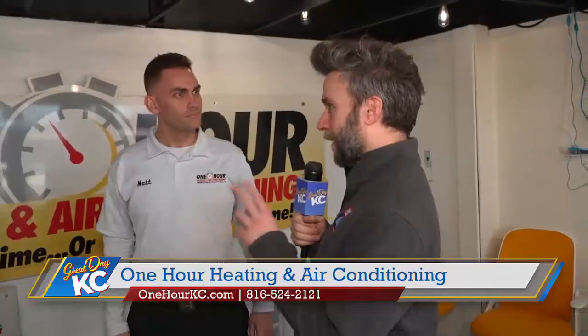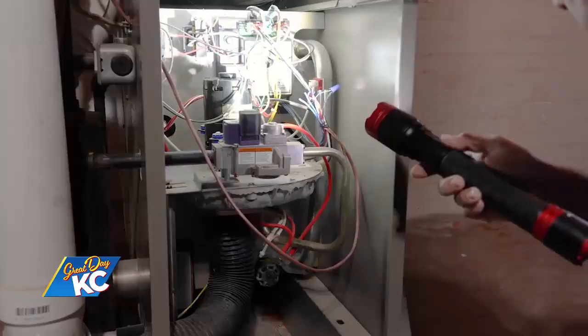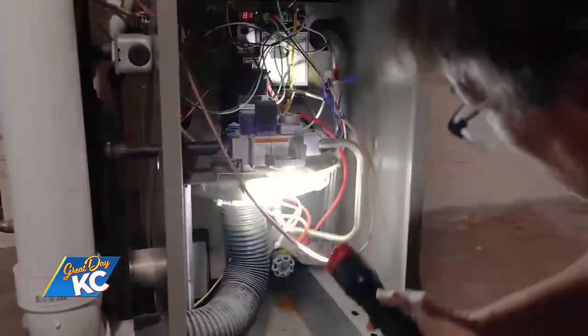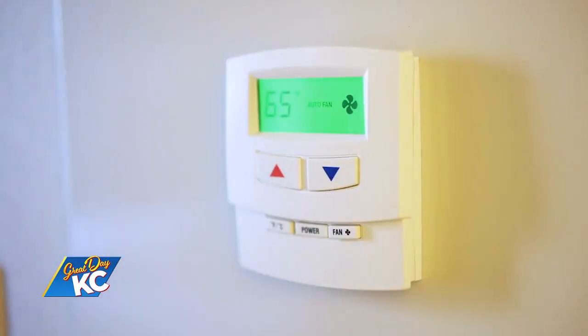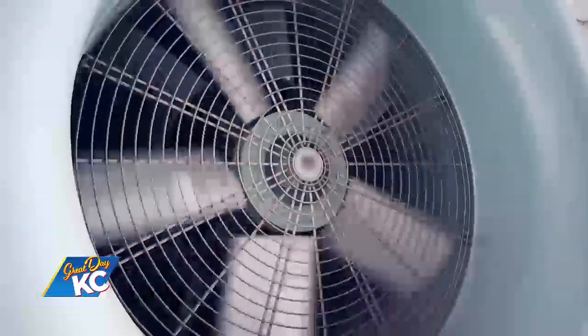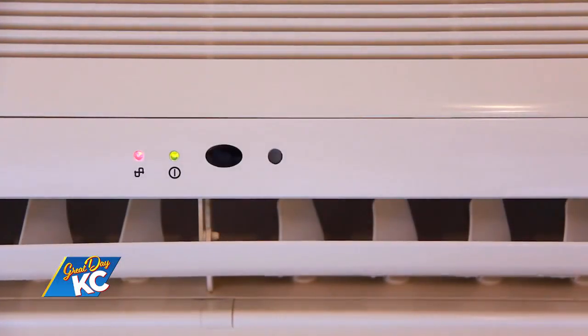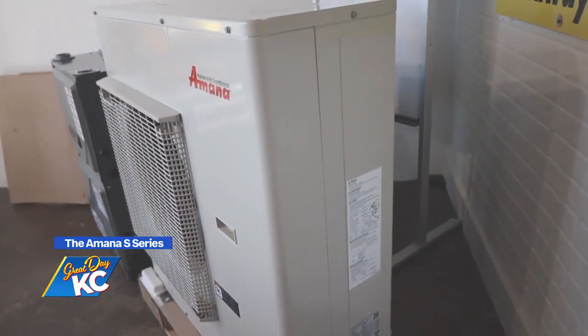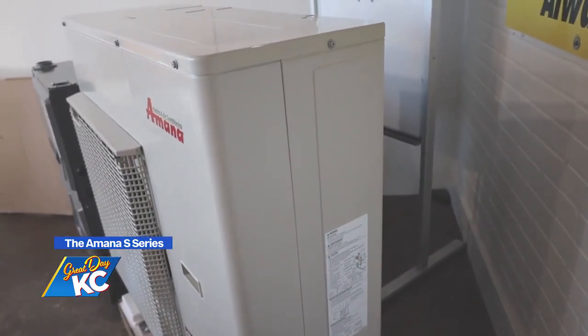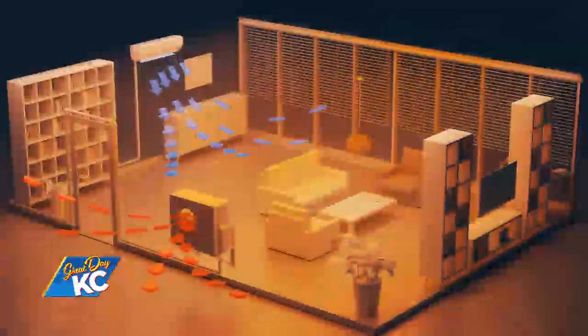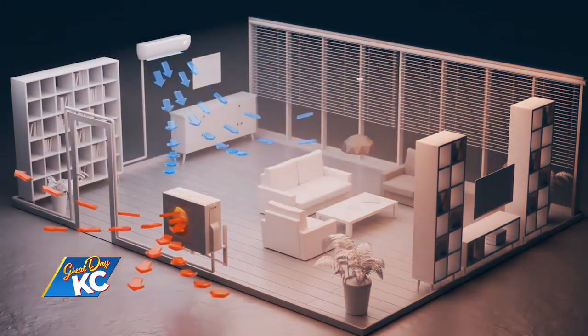How is a variable speed compressor different from a standard AC or a heat pump? A standard AC and a heat pump come with what's called a single stage compressor. When you hit your thermostat on, it comes on full blast, 100% airflow out of the vents, as cold as possible until it reaches temperature. With these, the compressor has a window of operation from 10% all the way up to 100% of its range. It's designed to put out the exact heat flow or cooling that you need into the home at that time. They have a longer run time, but it's called a swing compressor. They can go up and down depending on the actual need for the home.